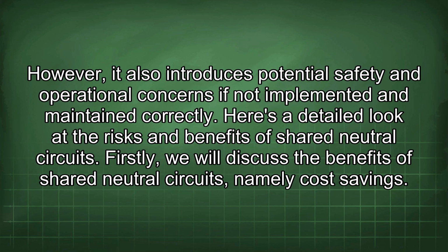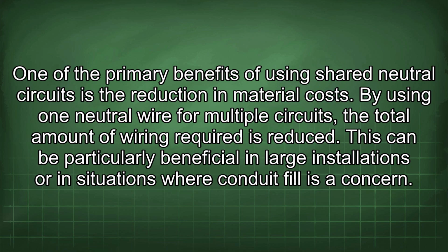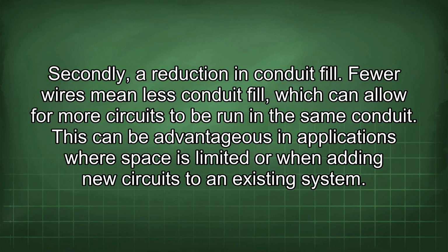Firstly, we will discuss the benefits of shared neutral circuits, namely cost savings. One of the primary benefits of using shared neutral circuits is the reduction in material costs. By using one neutral wire for multiple circuits, the total amount of wiring required is reduced. This can be particularly beneficial in large installations or in situations where conduit fill is a concern. Secondly, a reduction in conduit fill. Fewer wires mean less conduit fill, which can allow for more circuits to be run in the same conduit. This can be advantageous in applications where space is limited or when adding new circuits to an existing system.